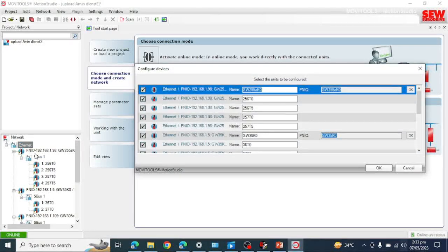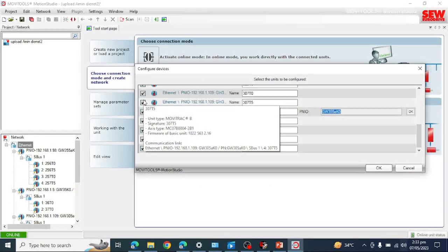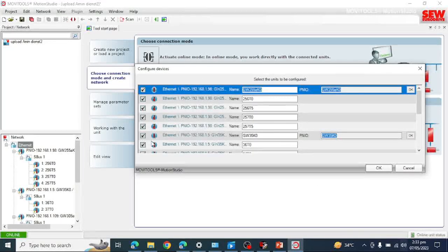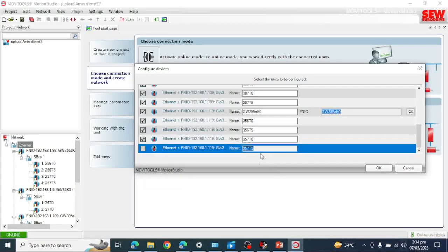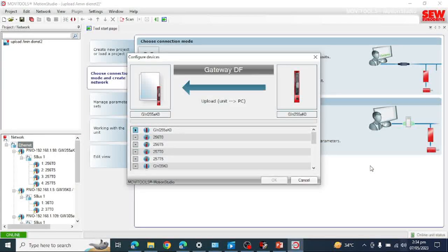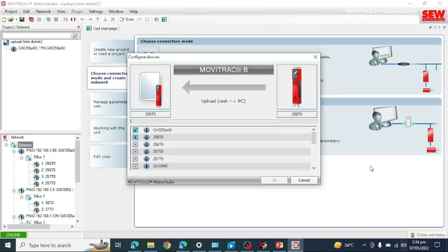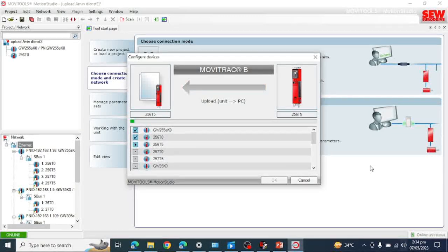Now what you have to do to configure all the backups: right-click on Ethernet and click Configure. It is now showing all the connected devices with tick marks, which means it will take backup of all these drives. I am deselecting one drive — I will show you how to upload a single drive backup later. I am clicking OK. Now you can see it is uploading the backup of all selected drives one by one into a single file.